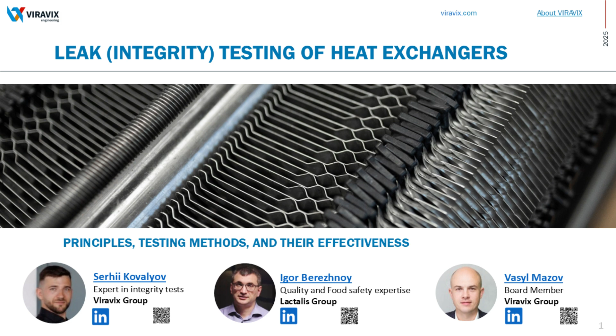Fluorescent non-disassembly method. The principle of this method is as follows. A special fluorescent dye is added to one of the heat exchanger circuits, where it distributes evenly throughout the system. Then, working pressure is applied, and the heat exchanger is held under these conditions for 30 minutes or slightly longer. After that, the unit is inspected in a darkened room using an ultraviolet lamp. At the leakage points, the dye glows, allowing precise identification of defects.